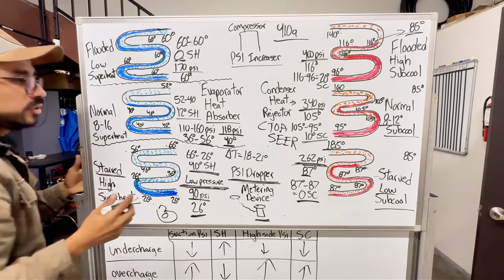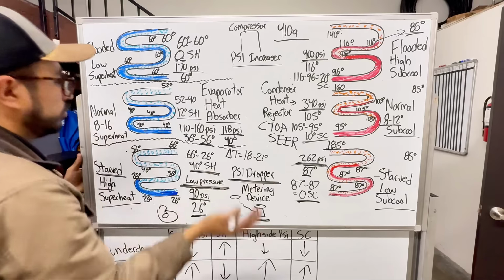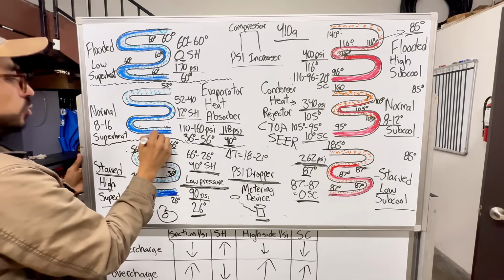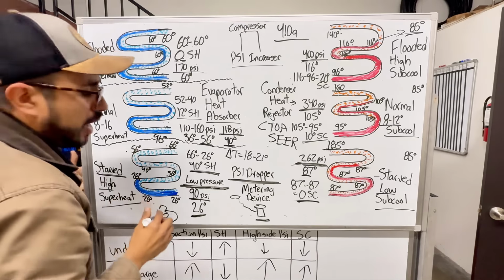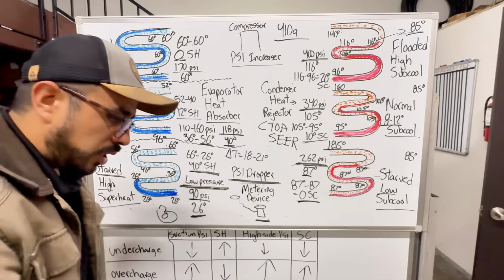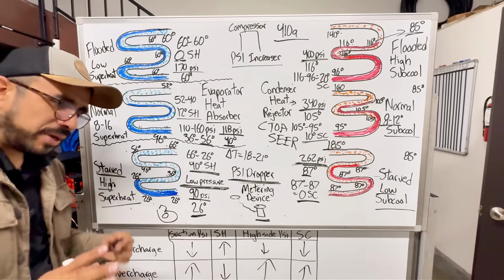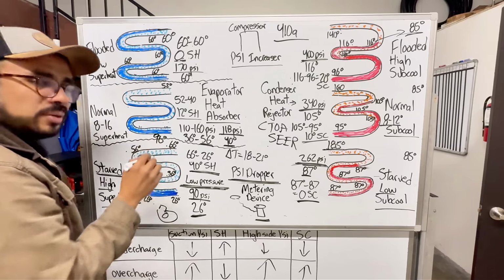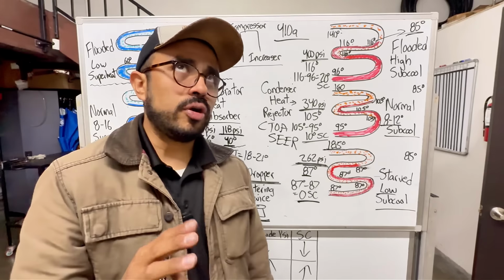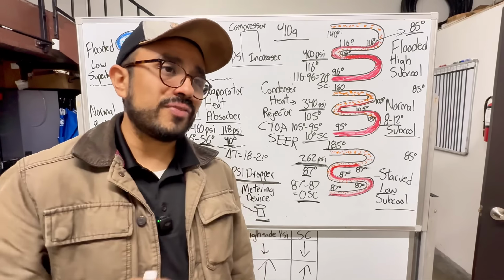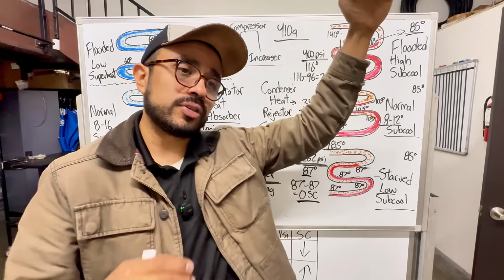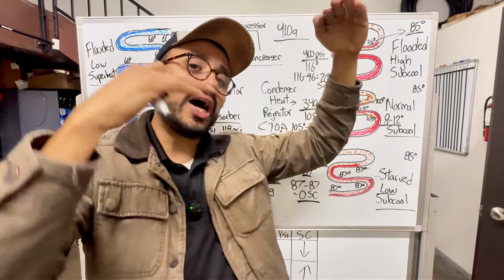If it's a hot house, you're dumping more refrigerant, right? More refrigerant on this side. Let's say it's 96 degrees. And there's something called approach. Typically, and I think it depends on the system you're working on, right away, if you get the return air temperature and you subtract 30 or 35, that should be your evaporator temperature.